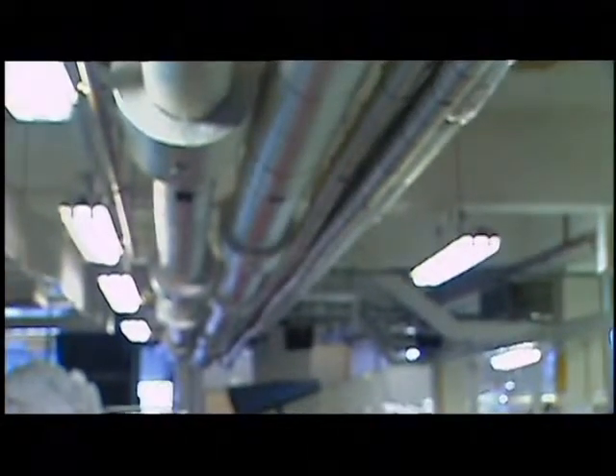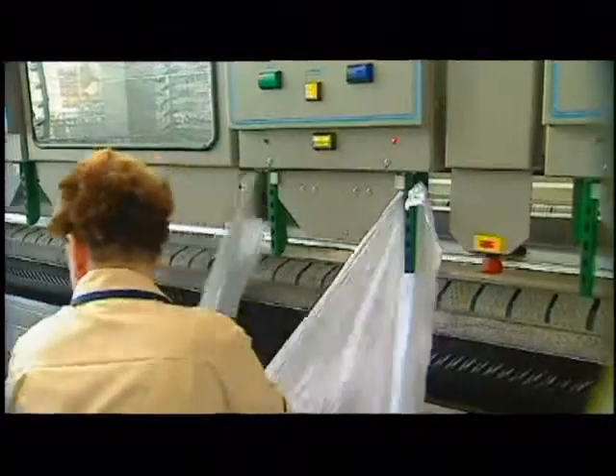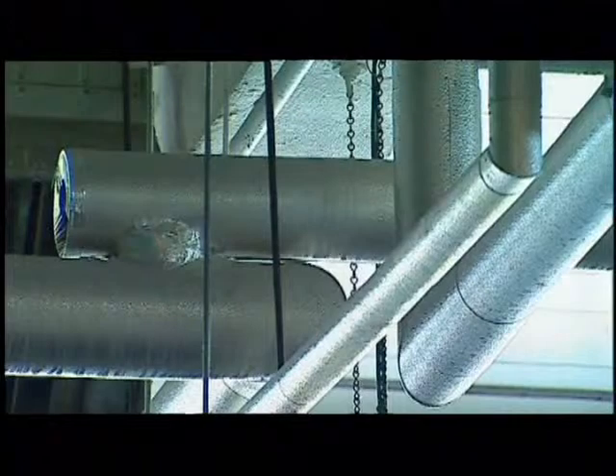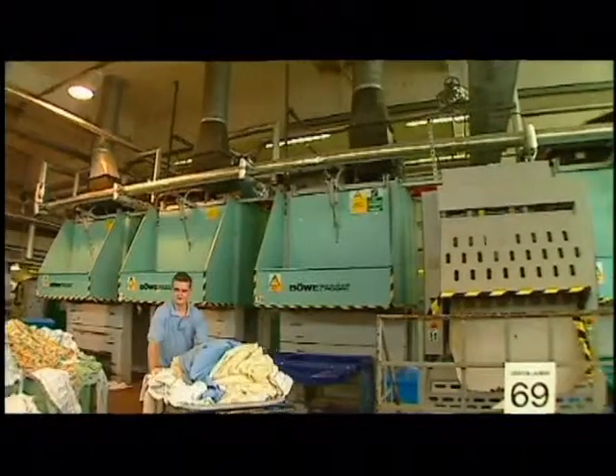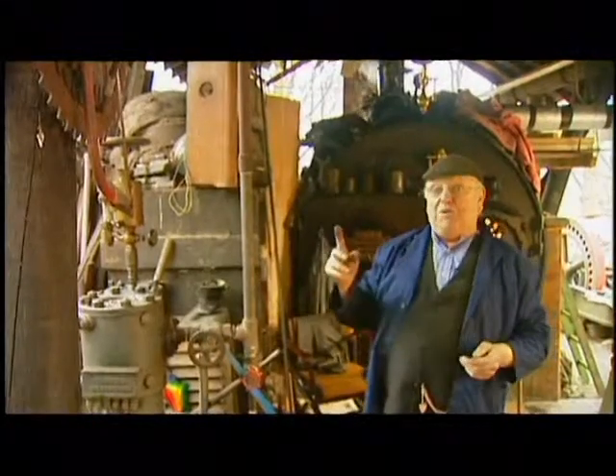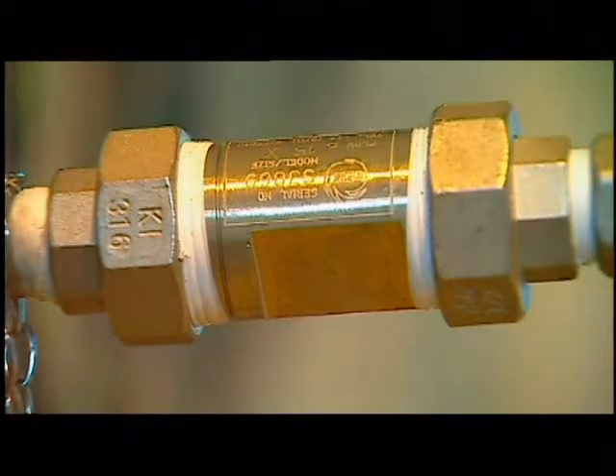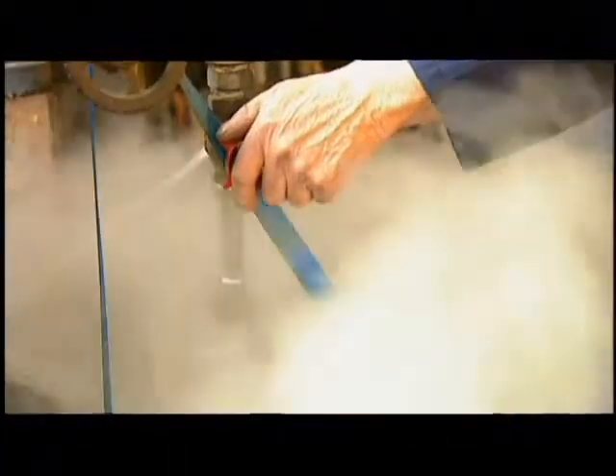But what exactly does a steam trap do? With any great length of steam pipe in a big works, as soon as the steam leaves the boiler and gets into the length of pipe, it condenses into water. You can have literally gallons of water in the system. The steam trap is the invention that gets rid of the water but leaves the steam in the pipe.